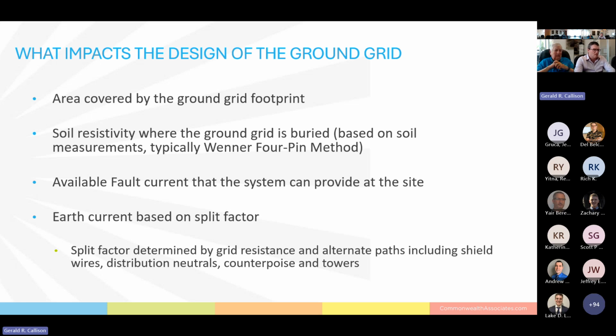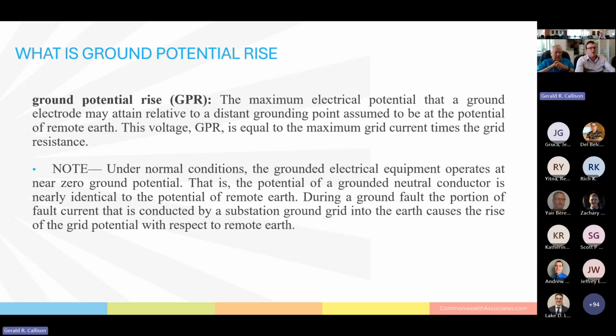So with that, let's talk a little bit about ground potential rise. It's a term that is going to be tossed around quite a bit during this presentation. What is ground potential rise? Ground potential rise is the maximum electrical potential that a ground electrode may attain relative to a distant grounding point assumed to be at the potential of remote Earth. This voltage, GPR, is equal to the maximum grid current times the grid resistance. That was a standard definition that I just read to you.